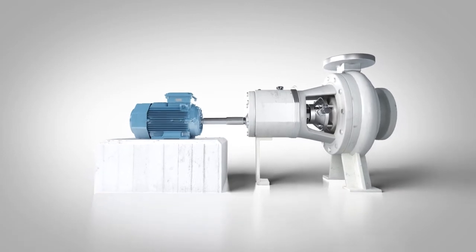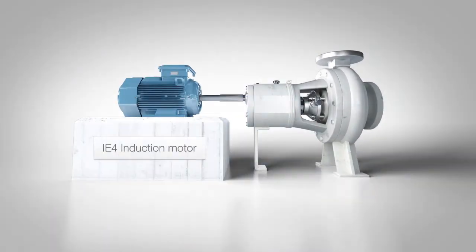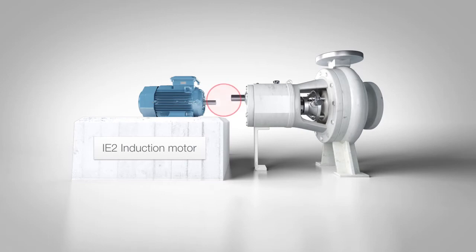However, a significant amount of active material have to be added in the induction motor. This means that IE4 induction motors may no longer be mechanically interchangeable with IE2 induction motors.